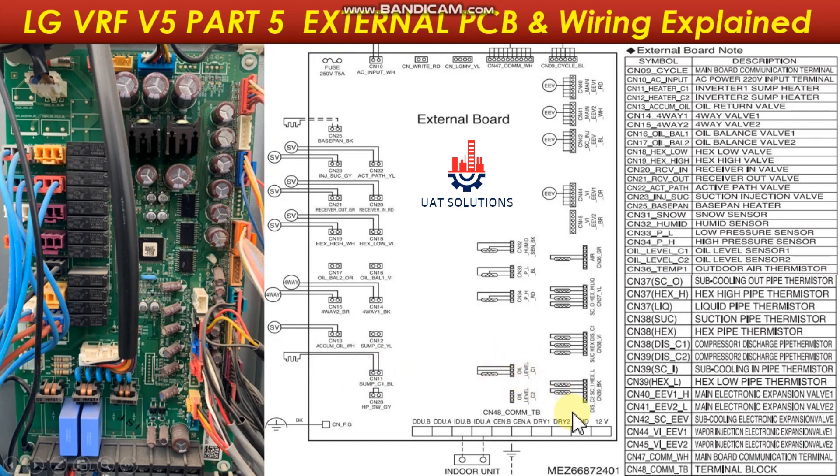Compressor 2 discharge temperature sensor is connected at port CN39 DIS C2. The sub-cooling pipe thermistor is connected at port CN39 SC1. The suction pipe thermistor is connected at CN38 SUCK. The HEX pipe thermistor is connected at CN38 HEX C1. Compressor 1 discharge temperature is connected at CN38 DC1. The sub-cooling out thermistor is connected at CN37 SC0. The HEX high pipe thermistor is connected at CN37 HEX.